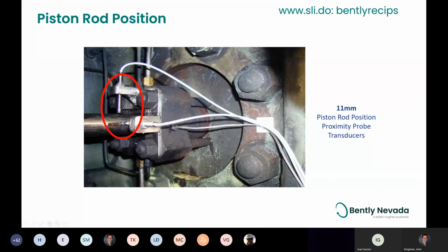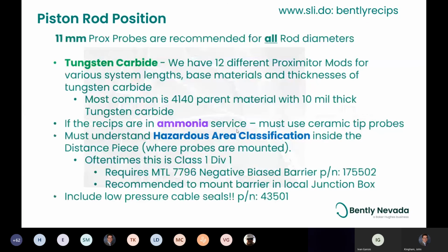And the probes are true horizontal and true vertical. We don't call these XY, we call them horizontal and vertical for a reason. And we also don't move the orientation away from 0 and 90. It just does not work at 45s.